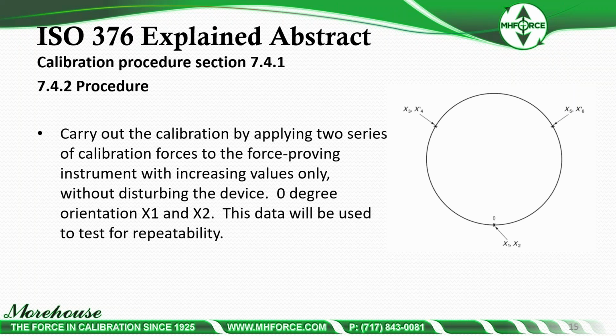And the procedure in 7.4.2 is carry out the calibration by applying 2 series of calibration forces to the force proving instrument with increasing values only, without disturbing the device. 0 degree orientation, X1 and X2. That's down here. That data is going to be used to test repeatability only. So we're going to take the instrument, we've already exercised it, and then we're going to put it in the 0 position. And then we're going to do our 8 to 12 forces. Remember, we recommend 12, ISO only requires 8. And then we're going to do them a second time without disturbing the instrument. And that's going to give us our X1 and X2 value.